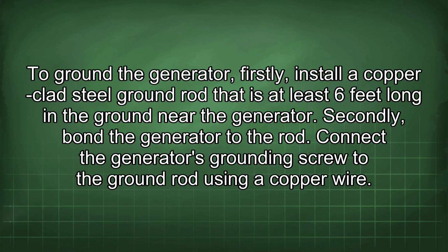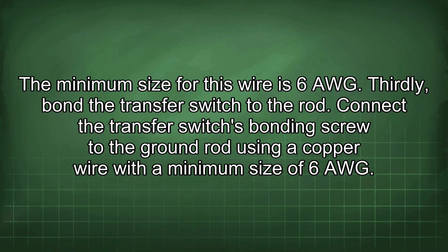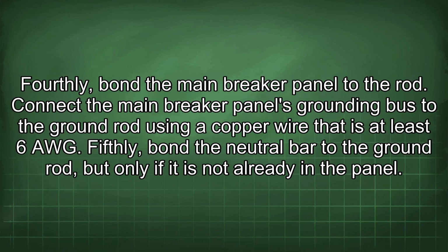Connect the generator's grounding screw to the ground rod using a copper wire. The minimum size for this wire is 6 AWG. Thirdly, bond the transfer switch to the rod. Connect the transfer switch's bonding screw to the ground rod using a copper wire with a minimum size of 6 AWG. Fourthly, bond the main breaker panel to the rod.